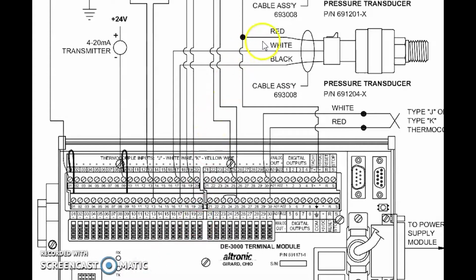We have our voltage supply wire, which is a red wire, and this is where the pressure transducer receives a constant, steady, true 5 volt supply. We have a black wire, which is connected to ground, and it can be grounded at the actual channel that it's associated with, or in a lot of cases, if you have an Altronic panel, the ground wire will be grounded to a common bus that has one wire but ties to what we call the A common ground terminal. And you can see the little ground symbol right here on the DE-3000 board. The last wire is white, and it carries the actual variable voltage signal back to the associated channel.